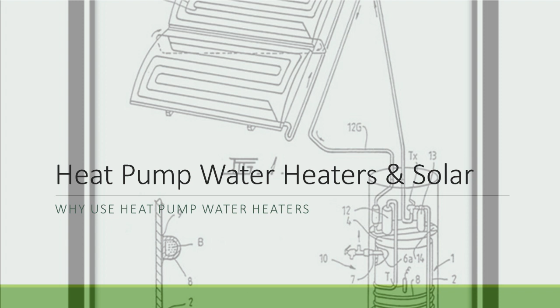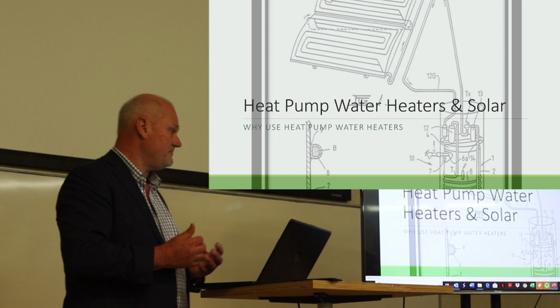The coil itself is effectively bonded to the tank, so the heat has nowhere to go. The tank is insulated with about an inch of insulation, so the heat goes into the water. This increases the surface area of the heat exchanger, but the amazing thing is it takes away issues to do with scaling, which plagues all heat pump water heaters. It also takes away issues with pumps and controllers, because it's a basic mechanical thermal system that can control itself.